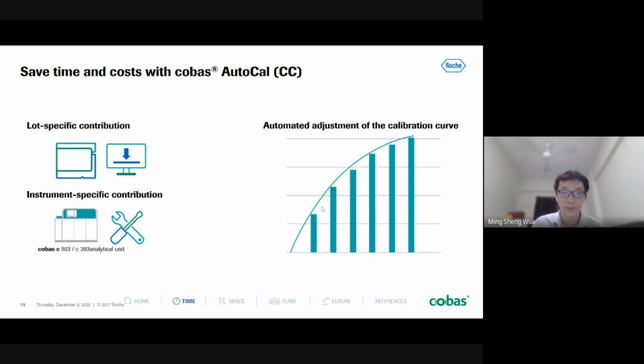and then the analyzer will plot the graph for you. With the Cobas Pro and also the Cobas Pure Analyzer series, if today you receive a new lot of phosphate, what you need to do is just load the reagent onto the analyzer. Then the analyzer itself will be able to register this reagent. From there, when you want to do the calibration, you just go to the calibration screen and press calibrate or press download. With that, the analyzer is able to automatically plot the calibration curve for you. Instead of needing to prepare all those calibrators manually and run the calibration manually, this can all be done by downloading the calibration curve directly from the analyzer itself.